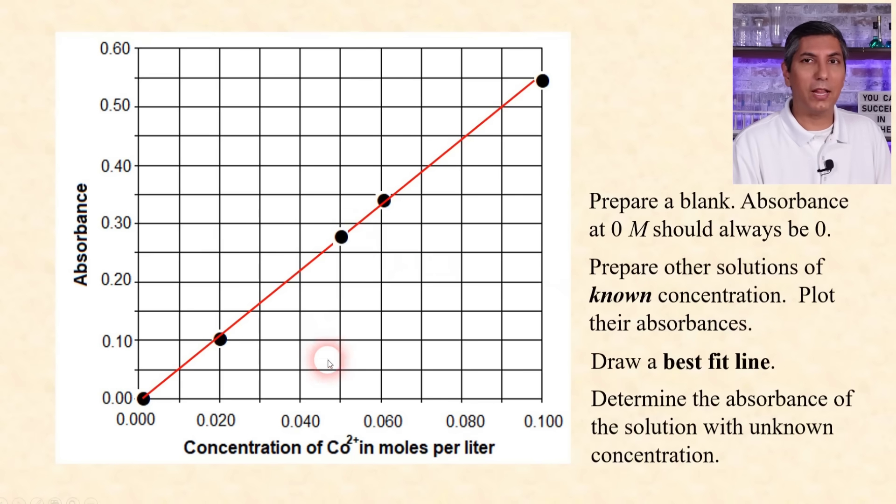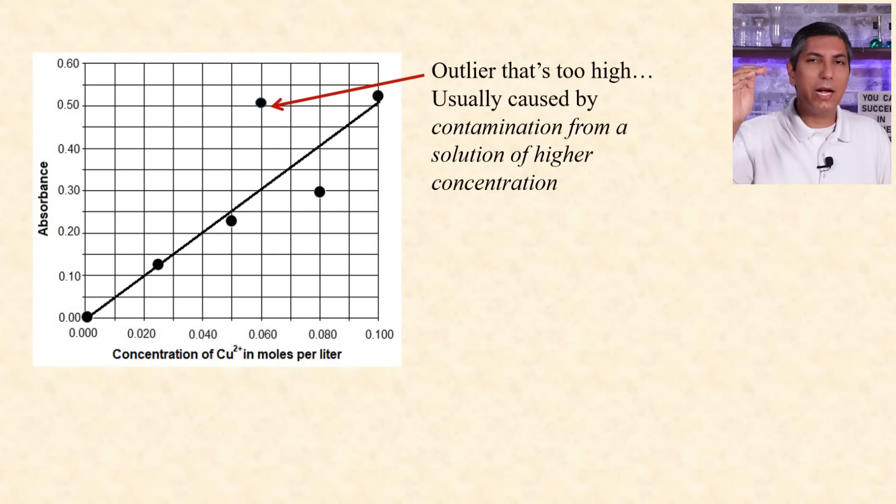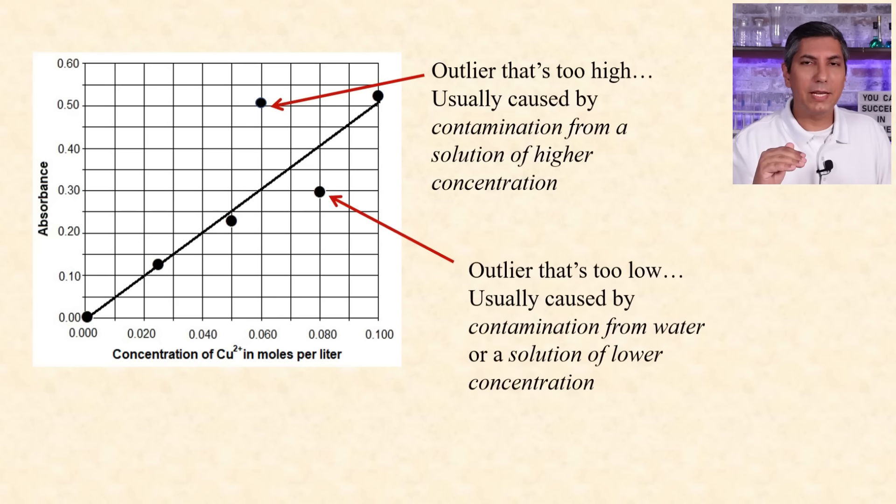If you have outliers on your calibration curve, there's usually a reason. If you have a dot that's too high, it probably got contaminated with a more concentrated solution. If a dot is too low, it probably got diluted with a more dilute solution, or very likely with water.